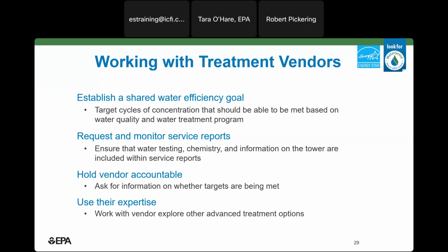Third, be sure that you're reviewing the service reports that they provide to make sure that they're achieving the cycles of concentration goals that you've both established together. So sometimes there's very valid reasons why these target cycles aren't being met, such as a mechanical failure. However, sometimes it's just a result of them not paying attention and not doing exactly what you hired them to do. So be sure to request these reports and review them regularly to make sure that they're meeting your goals.